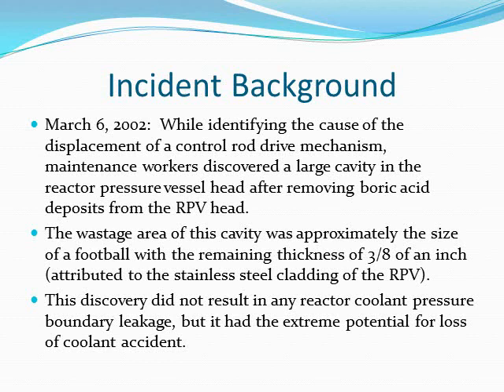The wastage area of this cavity was approximately the size of a football, with the remaining thickness of three-eighths of an inch, which was attributed to the stainless steel cladding of the reactor pressure vessel. This discovery did not result in reactor coolant pressure boundary leakage, but it had the extreme potential for a loss of coolant accident.